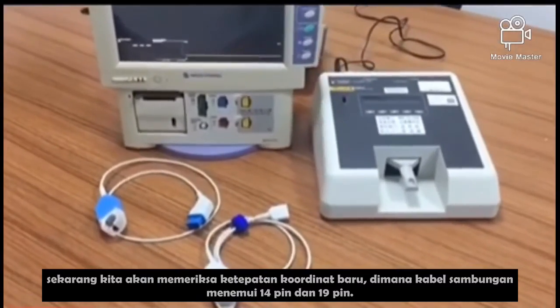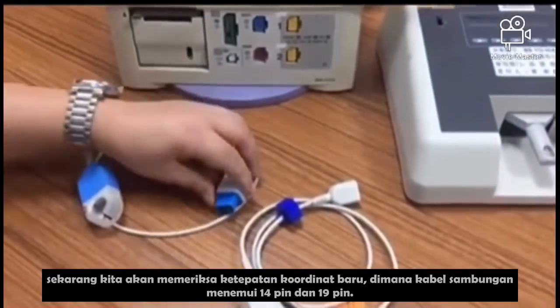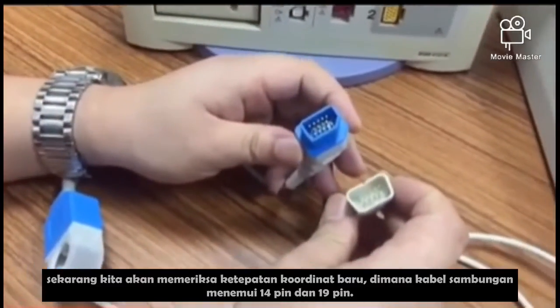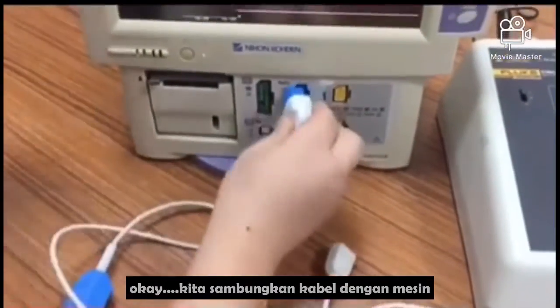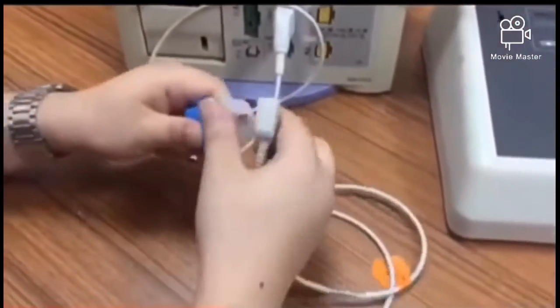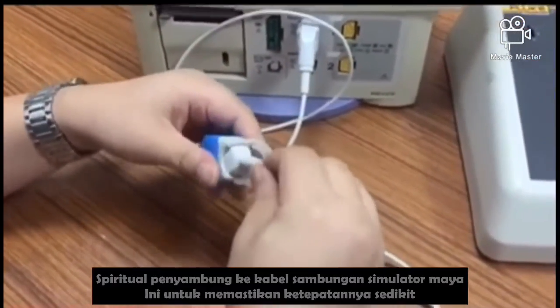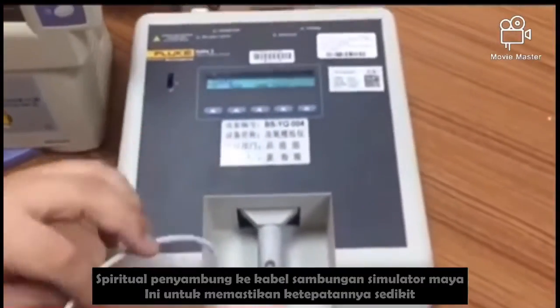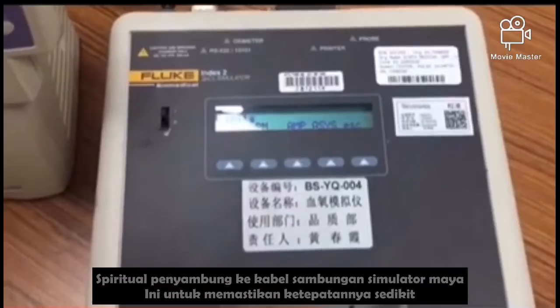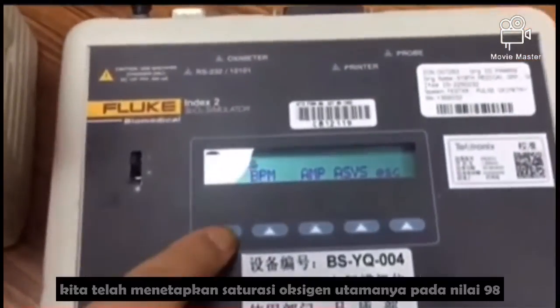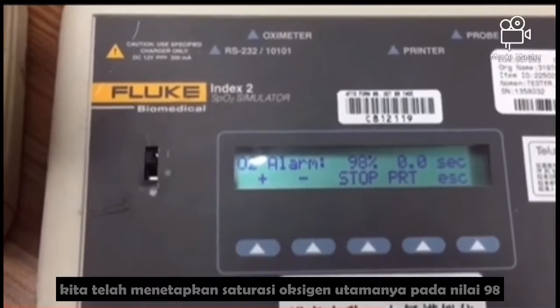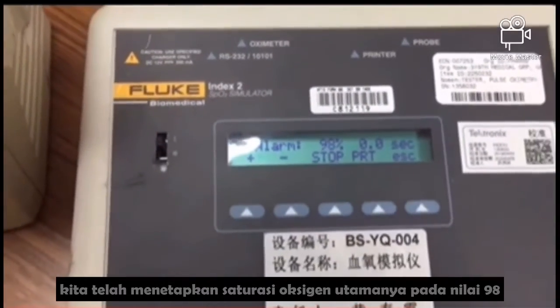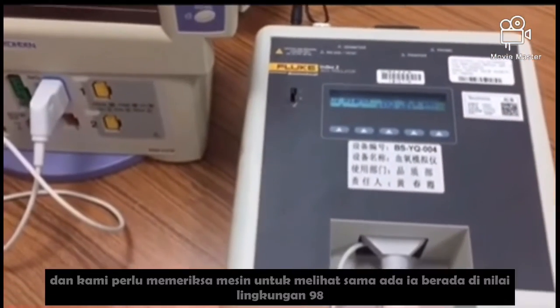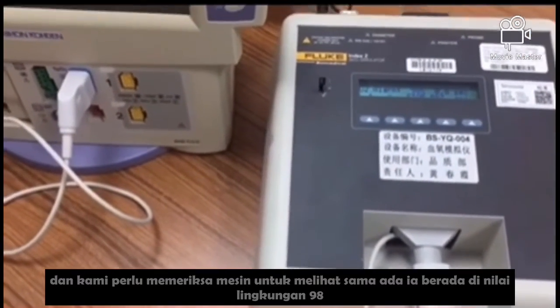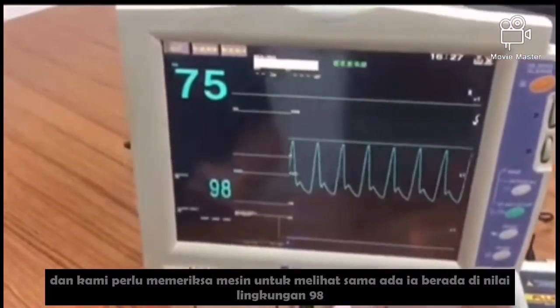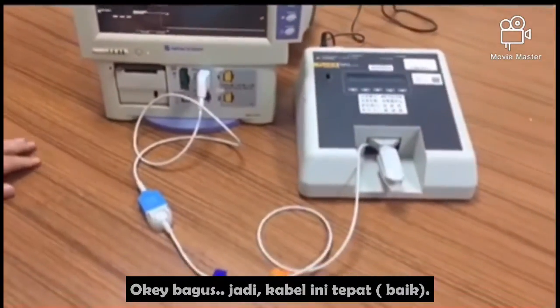Now we are checking the accuracy of the new SpO2 sensor and extension cable. New 14 pin and 19 pin. Okay. We connect the cable with the machine. SpO2 connected with the extension cable. This is the SpO2 simulator to check the accuracy of it. We have set the oxygen saturation at 98, and we needed to check the machine to see whether it is at 98. Yes, great. So this cable is accurate.